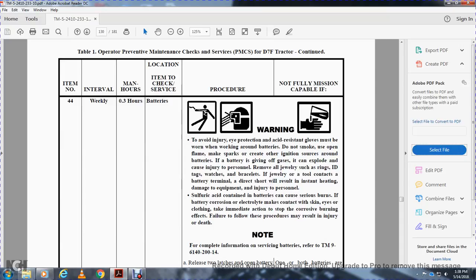Alright, item 44, 0.3 hours, batteries. Warning: to avoid injury, wear eye protection and acid resistant gloves when working around batteries. Do not smoke or allow flames, sparks, or other ignition sources around the batteries. If a battery gives off gas and explodes, it can cause injury. Personnel must remove all jewelry such as rings, ID tags, watches, and bracelets, and keep tools away from battery terminals. A direct short will result in instant heating, damage to equipment, and injury to personnel.